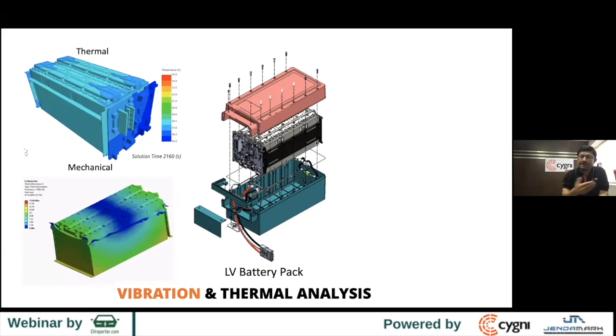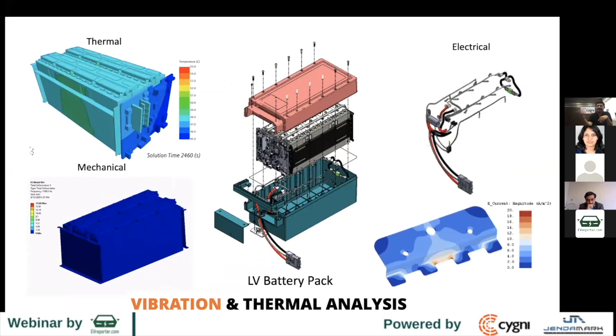How much of this deviation can happen, and is the pack designed for such deviation? These are all problems that have already been solved by others. All we need to do is make sure they are followed. And of course, the electrical condition - the bus bars, the interconnections, the local hotspots that happen if the bus bar thickness or width is not proper. All of this would not show up at the initial condition, but shows up over a few hundred cycles, and by the time you find out, it becomes too late.